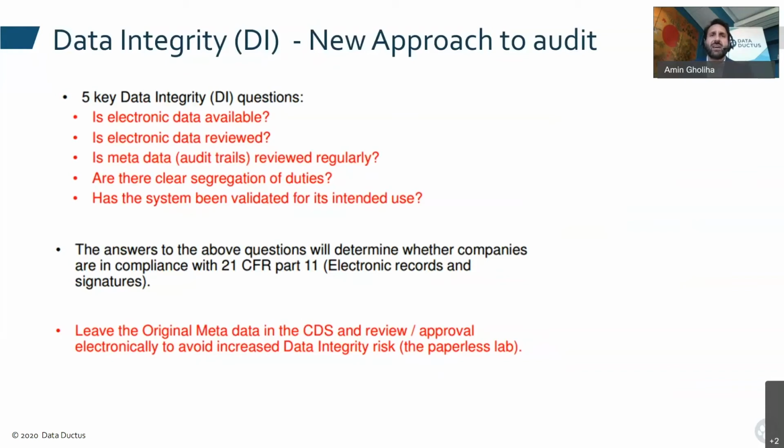Is electronic data available? Is the data reviewed? Is the metadata and audit trails reviewed, etc.? Regulatory, what I talked about before. Is there a clear segregation of duties, that users cannot grant password or authority to each other? And look at the validation documentation for the systems, of course. The answers to these questions will determine if the company is compliant with Part 11 or not.